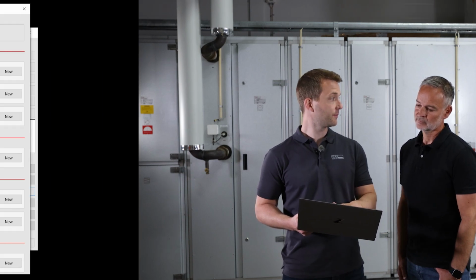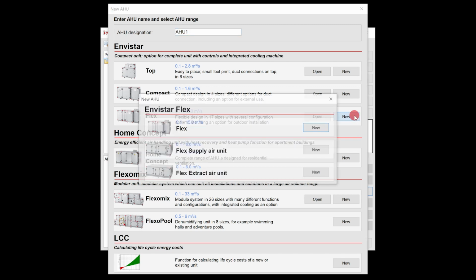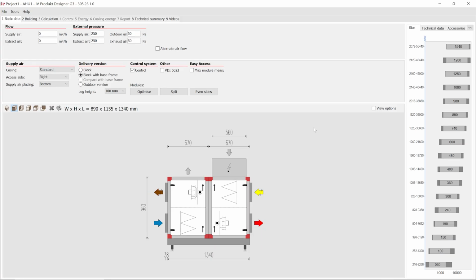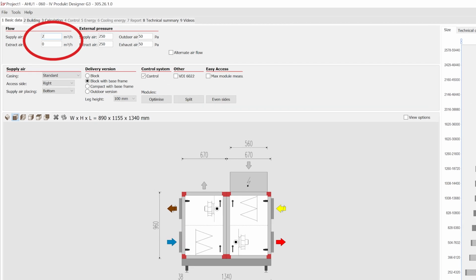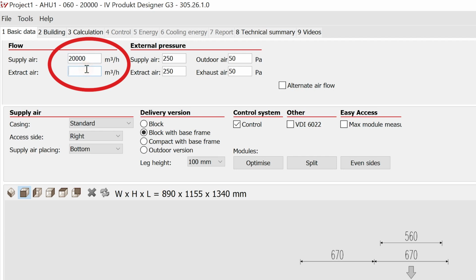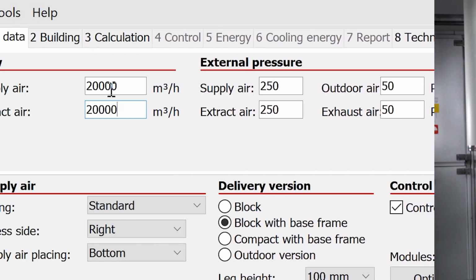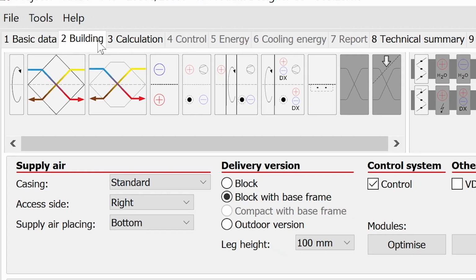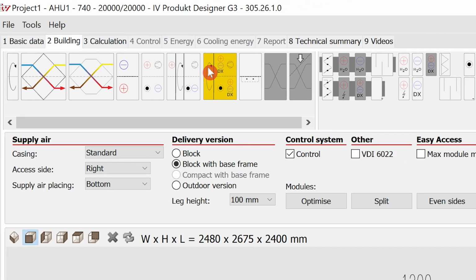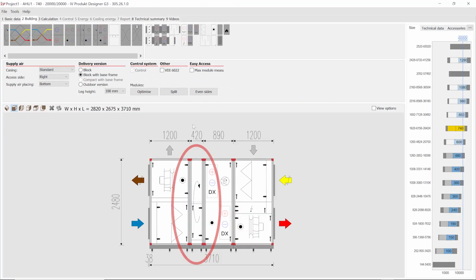Here in IV Product Designer, we can calculate the new unit, and we can make an investment calculation that will show the energy saving and the payback for this project. In this project, an Envistar Flex unit is suitable. Like we said, the airflow is 20,000 cubic meters per hour. Is 250 Pascal on the supply and extract air and 50 Pascal on the outdoor and the exhaust air okay? Oh, sure, that's good. Let's move on to the building of the unit. We select a rotary heat exchanger, which is the most efficient recovery unit.